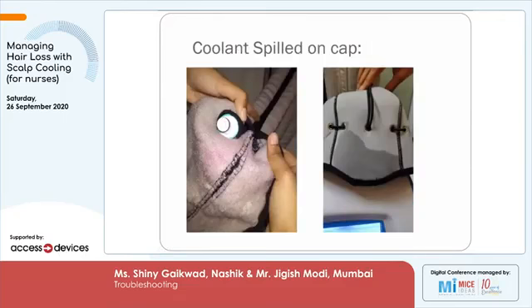Once it is ruptured, on the left side you can see the tubing has ruptured — the balloon which was there. The tubing has ruptured and the connector is split open, and the entire coolant has leaked out. When such a thing happens, kindly switch off the machine and call the engineer. Do not switch on the machine, otherwise all the coolant inside the machine will be pumped out.